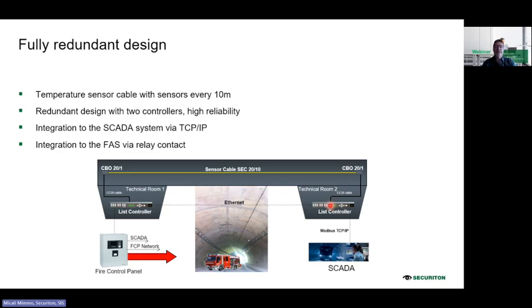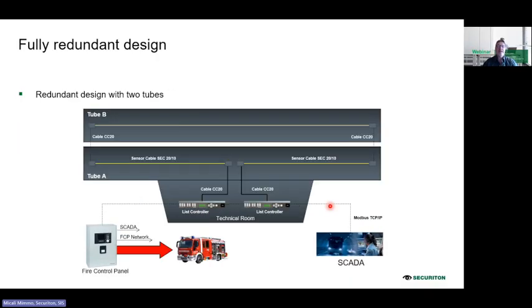This is what we normally always recommend when we do a design in a road or train tunnel, because in this case, even if there is a sensor failure or a controller failure, the system will still work without any interruption. And maybe if you have the same configuration as we saw before with the loop installation, instead of installing only one controller, you can open the loop and do the installation with two controllers. So you have redundancy on the controllers and also on the cable.